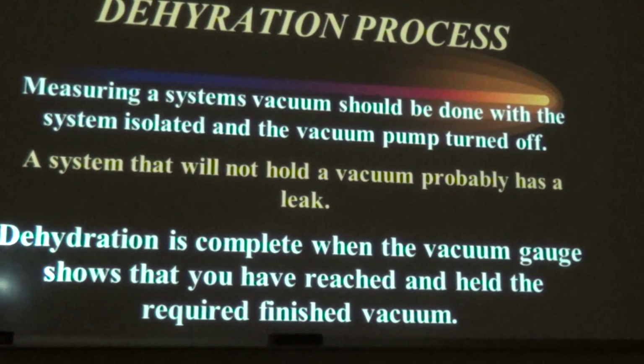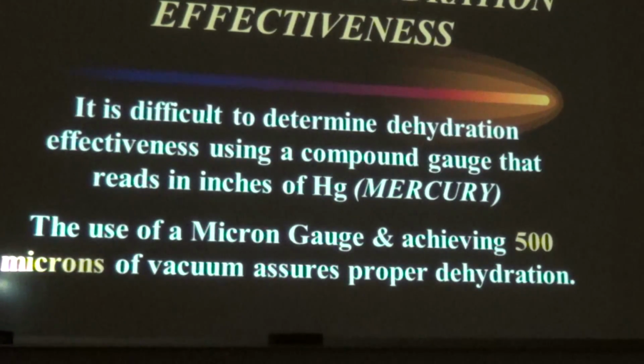A system that does not hold its vacuum level and goes back up to atmospheric pressure is going to be because it has a leak. The dehydration is finished when the vacuum pump with vacuum gauge shows that you have reached and held the required finished vacuum, and the next slide should be that number. It is. When do you know? It is difficult to determine dehydration effectiveness when you're using just your compound gauge that reads in inches of mercury. That's why they recommend that you use a micron gauge. And the number that you're looking for on your micron gauge is 500 microns of vacuum to assure proper dehydration. So 500 is the number you want to remember, 500 microns.